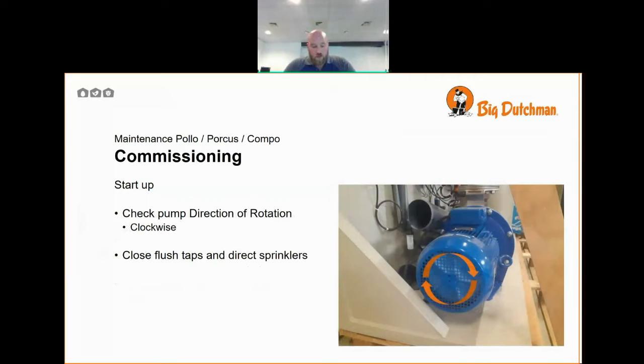One of the first things to do is to check the direction of rotation of the pump. This must always be clockwise. In the case that the pump runs in the opposite direction, you must reverse any two of the power phases on the pump.